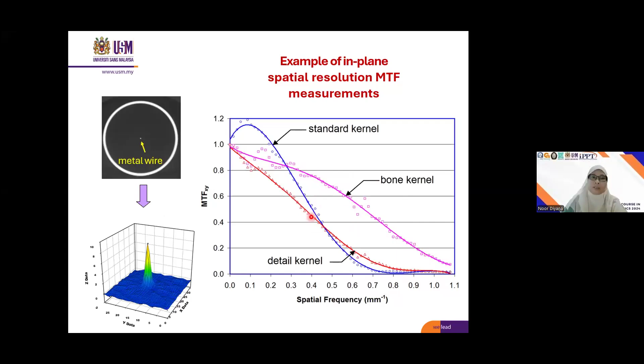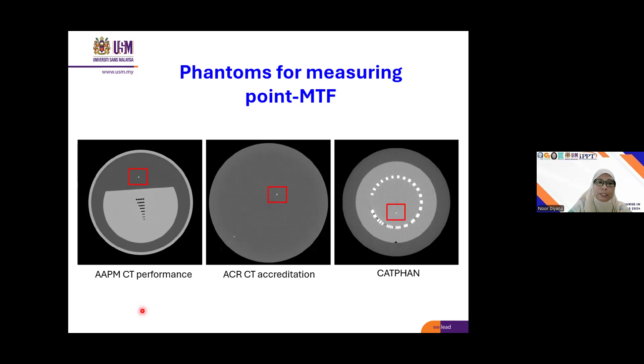To measure the point MTF, actually in each phantom, there is a point wire or metal wire inside that phantom. So this is for the AAPM phantom, this is for the ACR phantom, and this is for the CATPHAN phantom. So each phantom has the area or the point where you can measure your point MTF.